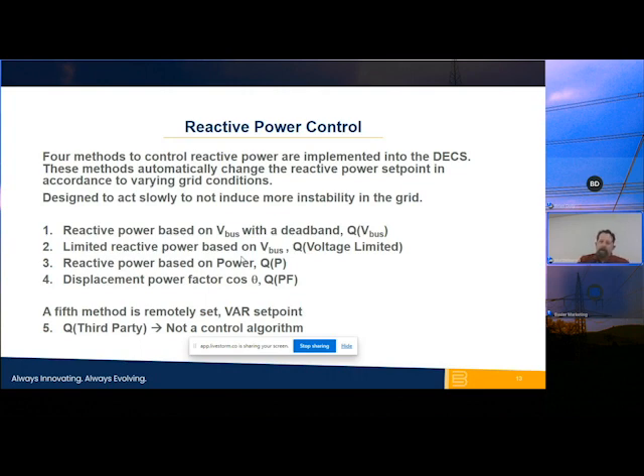into. Now, what happens is as the grid moves and we're trying to control the reactive component, we have to put limits on it to control the overall voltage, because by increasing or decreasing the amount of VARs or kVAR on that system, that voltage can be moved as well. So that's where the 4 points of that voltage limit come in. And that's our second mode of operation, which is QV limited.